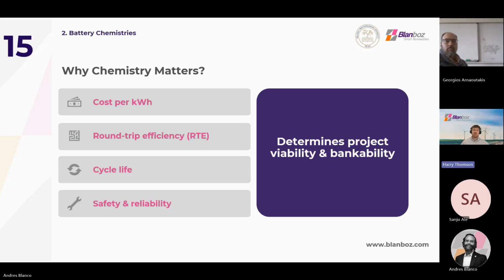This leads on to the cycle life, which again is fundamentally linked to the chemistry of the battery selected. Different chemistries have different tolerances for factors that impact degradation, including acceptable depths of discharge, rest time needed between cycles, and temperatures that can be sustained. This impacts the intended design life of the project and how the BESS shall be operated.